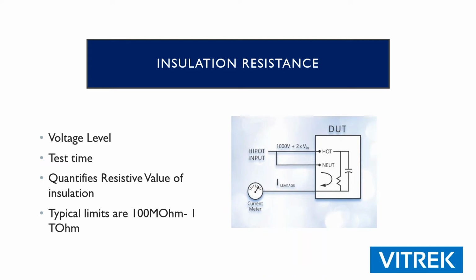But we're going to be, in IR, usually looking for somewhere above 100 megohms. In the gigs is pretty common. And these are usually done at a little bit lower voltages, usually 500 or 1,000 volts, sometimes as low as 50.